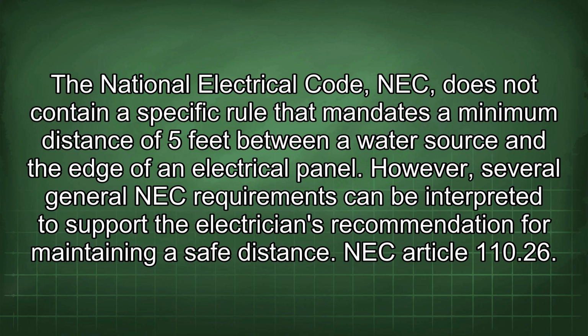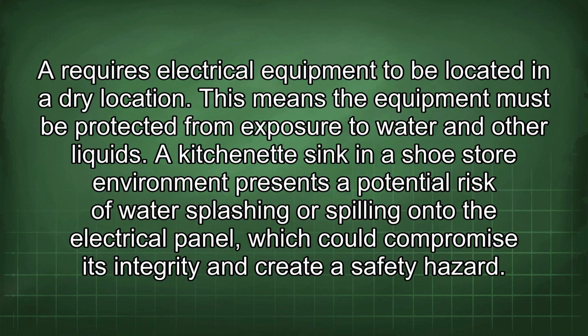NEC Article 110.26 requires electrical equipment to be located in a dry location, meaning the equipment must be protected from exposure to water and other liquids. A kitchenette sink in a shoe store environment presents a potential risk of water splashing or spilling onto the electrical panel, which could compromise its integrity and create a safety hazard.